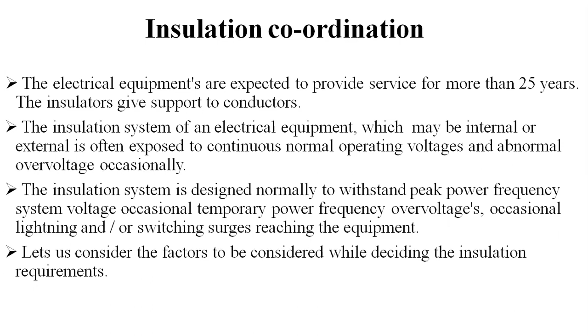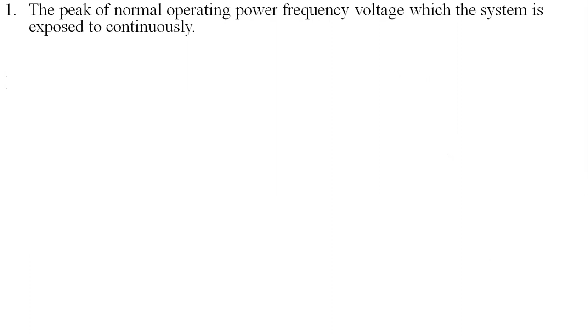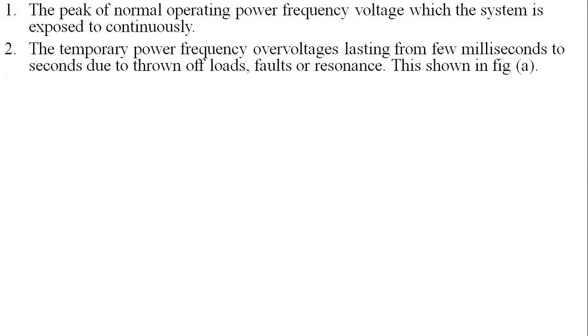Let us consider the factors to be considered while deciding the insulation requirements. First, the peak of the normal operating power frequency voltage which the system is exposed to continuously. Second, the temporary power frequency overvoltages, lasting from a few milliseconds to seconds, due to thrown off loads, faults or resonance. And this is the picture. See, this is the duration of our overvoltage, and there will be a temporary power frequency overvoltage over here for a period. Up to here it is a normal amplitude sine wave. From here, the voltage is a temporary power frequency overvoltage.